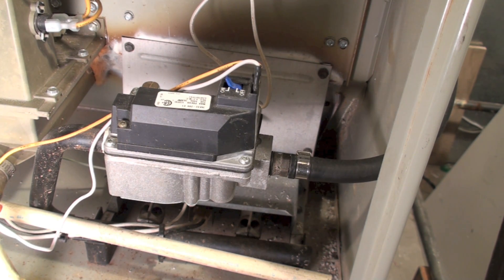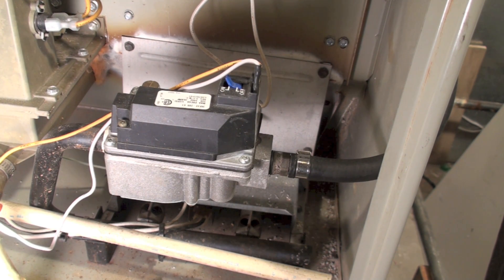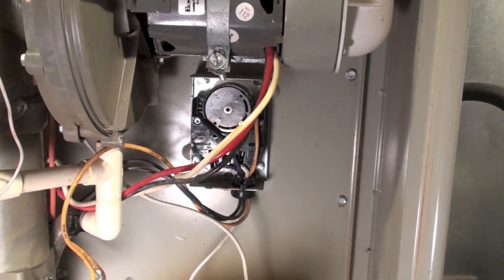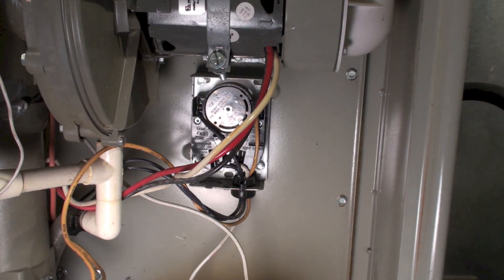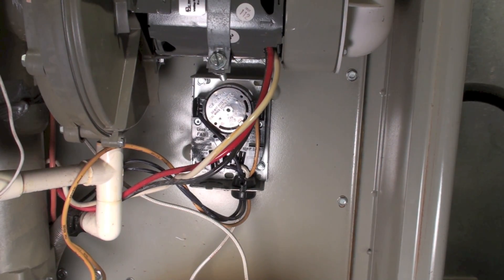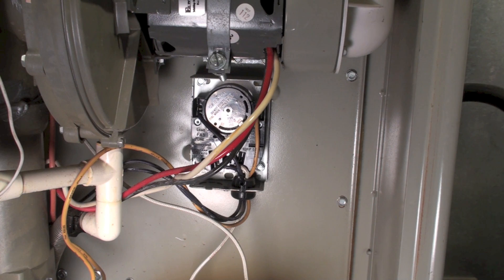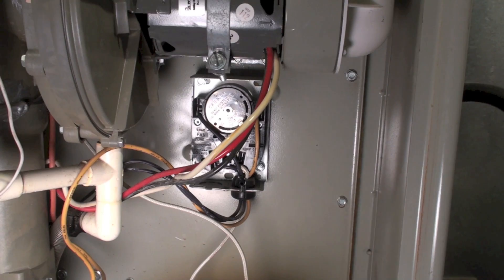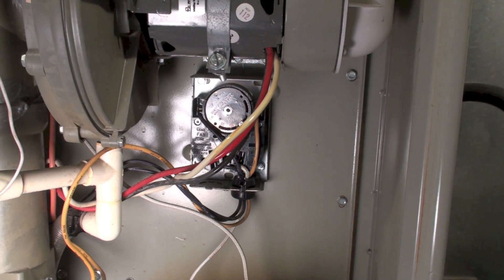Now we have our burners on, and we've got a heat-operated fan switch, just like on the older furnaces. The heat-operated fan switch has to warm up and turn on the circulating fan. That's pretty much the sequence on this thing. We'll dig into the burners and some of the other things in later videos.